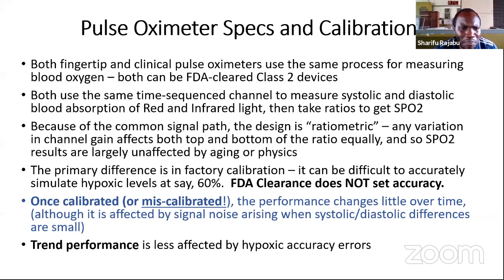The principle used by the pulse oximeter to take its measurement considers the ratio of oxygenated hemoglobin to deoxygenated hemoglobin. Due to that factor, almost all the error that may be due to aging of the pulse oximeter will be cancelled. So if the pulse oximeter is not accurate, or deviates so much from the true value, it usually means it was miscalibrated during the manufacturing process.